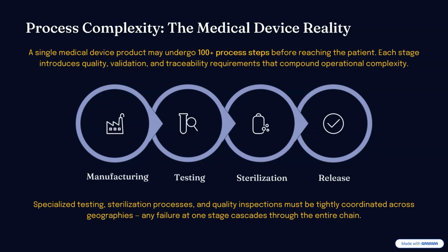The supplier cannot release it, because the standard says you have to have these values. In one recent case we waited 6 months to get it released, because the ETO values were so high and it could not be released for human use. So sterilization is not so simple. We think that it's very simple, but it's quite complicated. You need to plan the best sterilization method for your product.